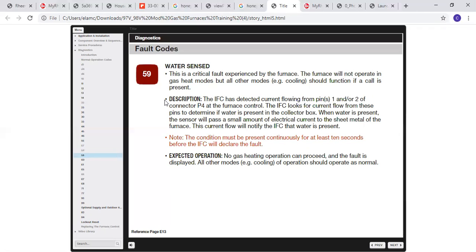So as far as it's concerned, the IFC has detected current flowing through pins 1 and 2 of, generally speaking, the lowest water sensor. As we discussed in the first one, it's a little needle there, so if you just have water splashing on it, it's not going to trigger this sense. If it's a true water sense situation, the water has to come up and basically sit in that sensor for at least 10 seconds. If it's anything less than 10 seconds, you won't get the water sensed. So it truly did have to trip some sensor of some sort.